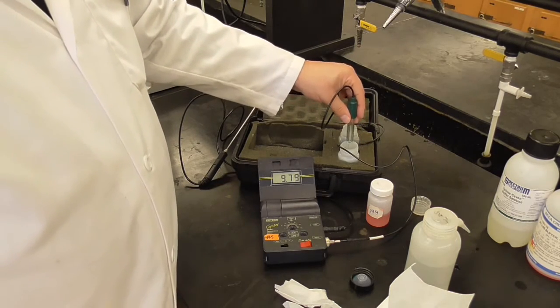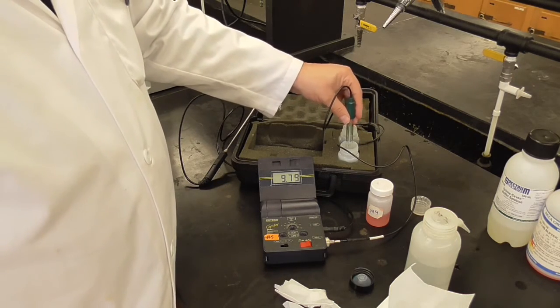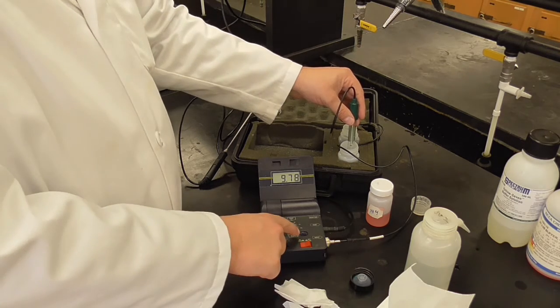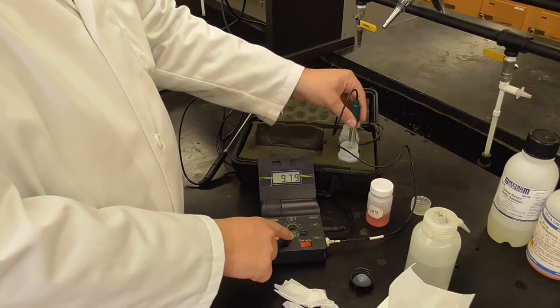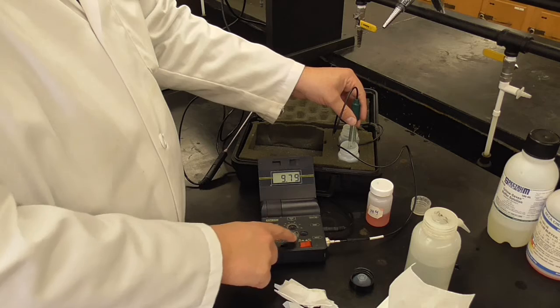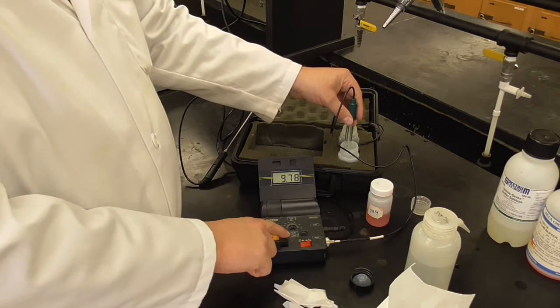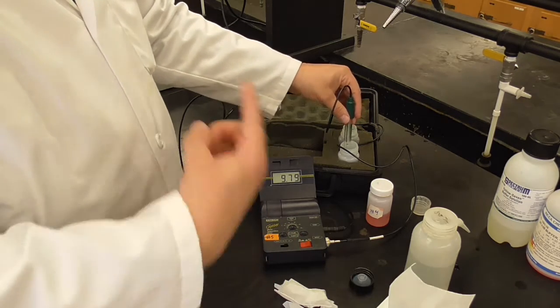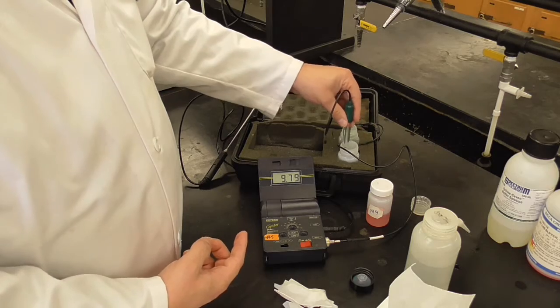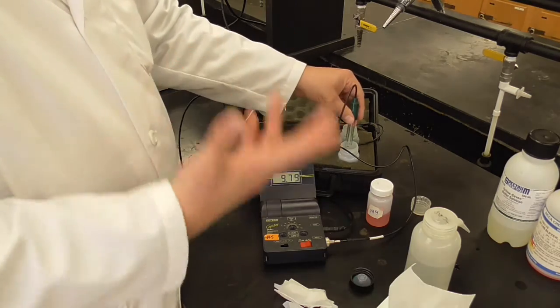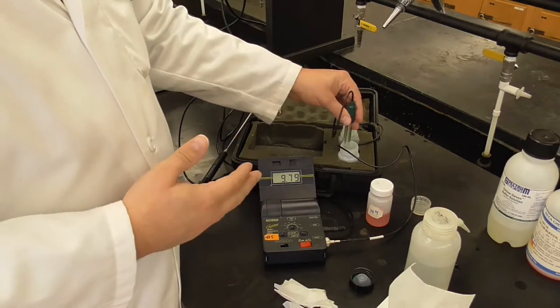Okay, and again, it's not reading 10, but it's close. This time I don't use the calibration button, I use the slope, which you can see this arrow points that way, because this is the second point of the calibration, right? So you're making essentially a straight line.